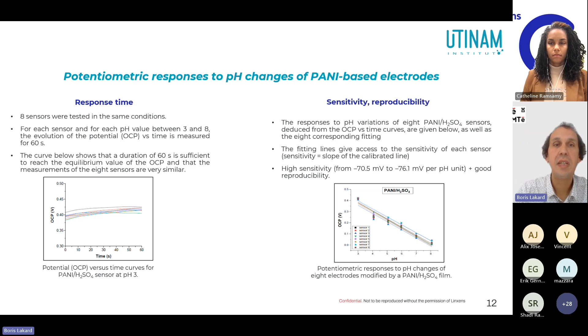On the right, the figure shows the evolution of the potential as a function of pH. The curves obtained were linear, and their slope can be assimilated to the sensitivity of the sensor. This figure clearly shows that the sensors have a high sensitivity, over 70 millivolts per decade, which is a high sensitivity.